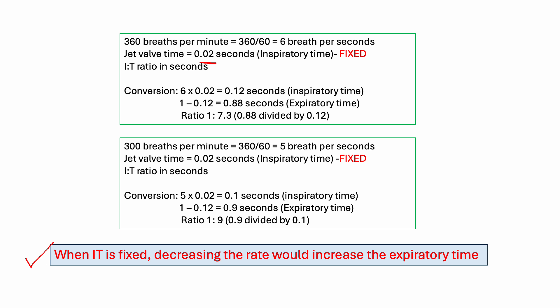Here is the calculation. At 360 breaths per minute, divide by 60 to get 6 breaths per second. The inspiratory time is 0.02 seconds. You subtract from 1 second to get the expiratory time, and then divide inspiratory time by expiratory time to get the I:E ratio.